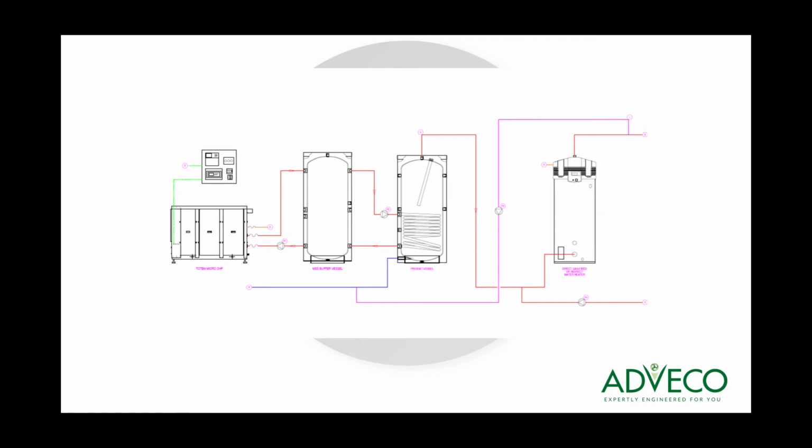Combined heat and power is typically coupled with the domestic hot water system to provide hot water to the building. It's done as a preheat system to give it the long heat up time in between the peak demands, and you have an afterheating system to make sure that at all times you can supply the hot water to the building. It shows there one water heater as an afterheater, but likely for a commercial building there would be two, and often they would be set to 60% each. So in the case of failure of one, you still have 60% of the load of the domestic hot water.